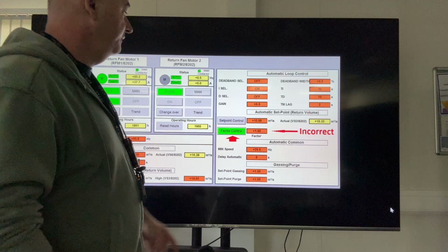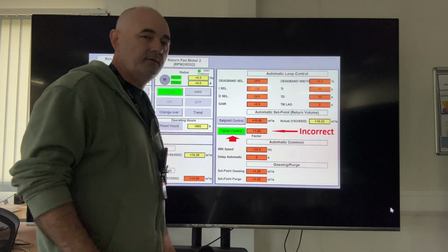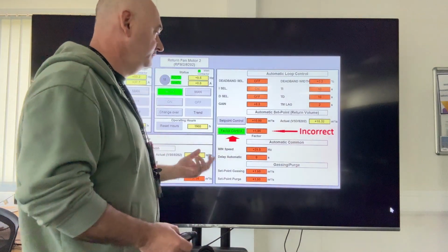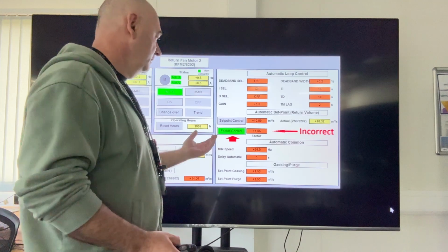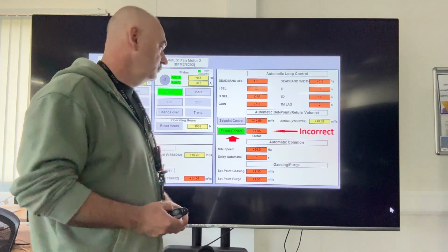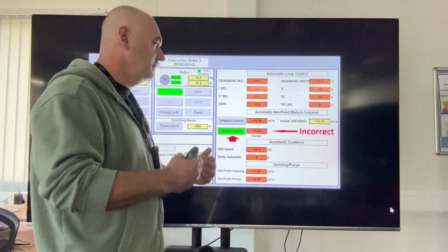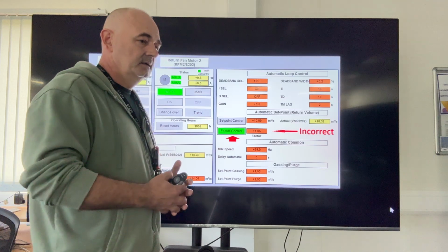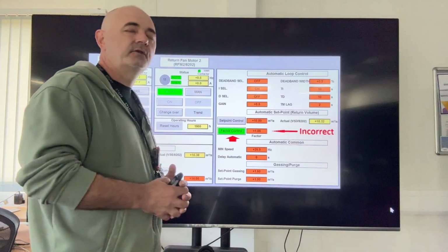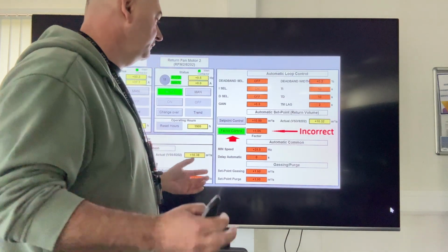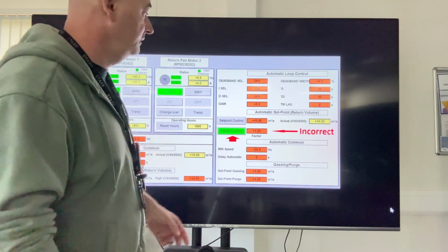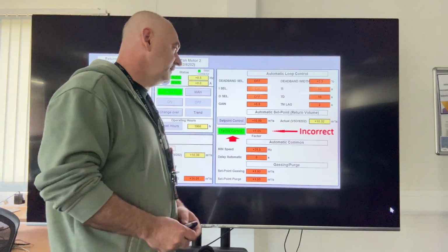Another issue I have is the factor control of 1.5. We all know that with factor control, I have to extract less than we push, but because of air coming from other rooms into this corridor, I think it's 230 and 200, a lot of air comes in, I have to run the extractor fan faster than the supply fan.